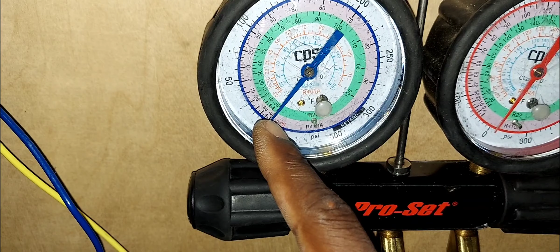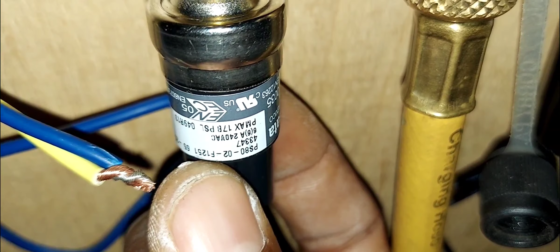Remember, this low pressure switch right here has a range on it. Rotate so you can see it. It closes at 65 and opens at 25. You can see that right there. Now this particular switch, our low pressure switch, is for an R22 system, refrigerant R22, potentially R407C. All right, because at 65 psi, it will close and allow the system to operate. At 25 psi or below, it will cut off as a safety to prevent the system from running while it's low on refrigerant.